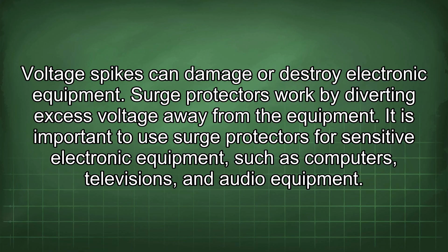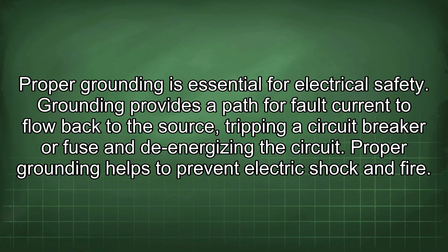Proper grounding is essential for electrical safety. Grounding provides a path for fault current to flow back to the source, tripping a circuit breaker or fuse and de-energizing the circuit, which helps prevent electric shock and fire. Bonding is the process of connecting all metal parts of an electrical system together, creating a low impedance path for fault current, which also helps prevent electric shock and fire.